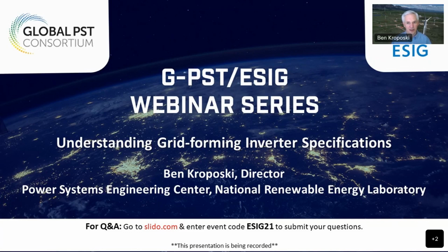Inverters, on the other hand, are not historically designed to provide that amount of fault current. If you wanted them to provide that amount of fault current, you would have to over-design several components in that system, and that would, of course, drive up some of the costs. That being said, you may be able to get away with having the inverters provide 1.5 or 2 times fault current instead of 6 times fault current.